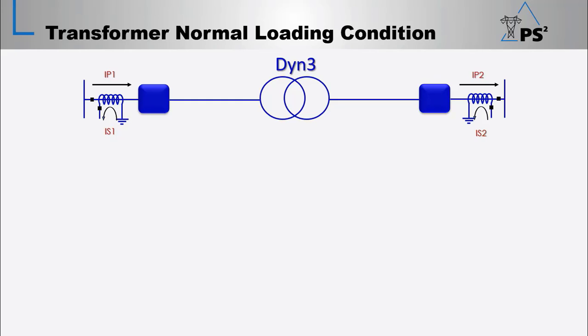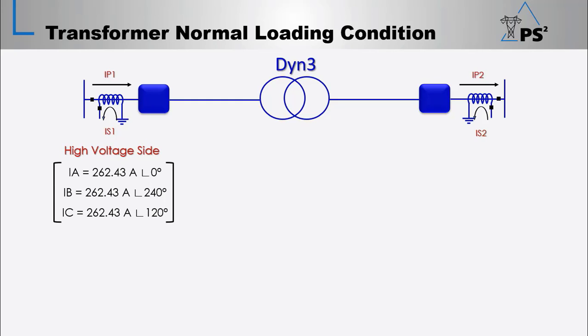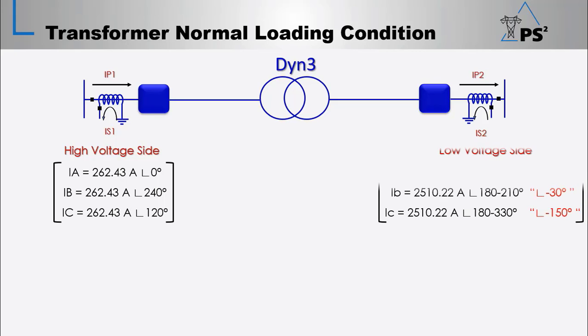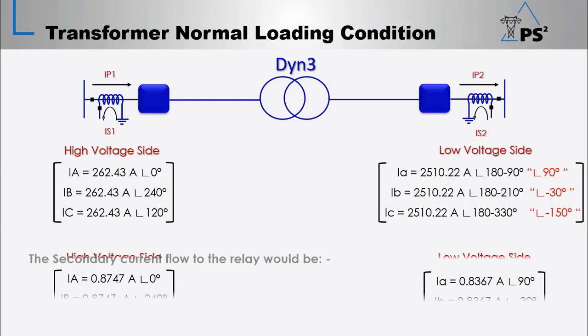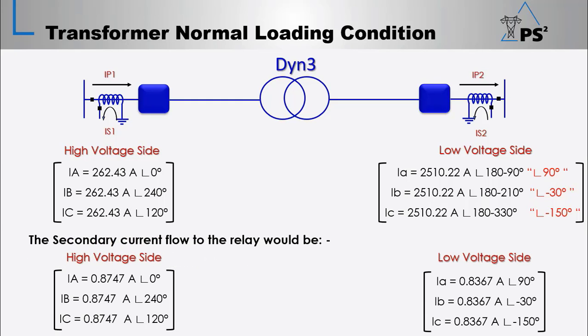The current flow during the full loading conditions would be, for the primary delta side, which is the high voltage side, the three-phase currents will equal 262.43 amps with balanced angles, acting as the relay reference winding. While for the secondary star side, which is the low voltage side, the three-phase currents will equal 2510.22 amps with balanced angles but lagging the high voltage side by 90 degrees as per the transformer vector group. Also, we can notice that the low voltage side terminals would have a phase shift of 180 degrees due to the CT star point direction and the CT connection to the relay. The secondary current flow to the relay according to the CT ratios would be 0.8747 ampere for the high voltage side and 0.8367 ampere for the low voltage side.